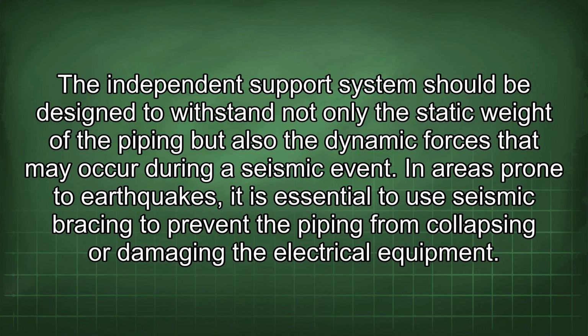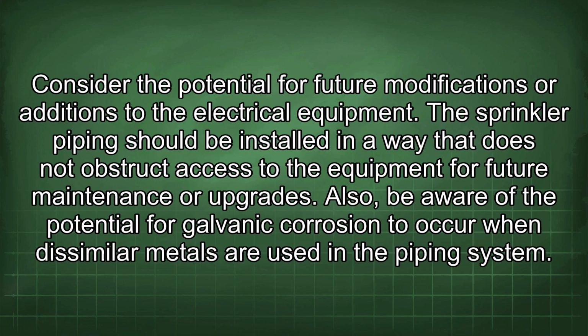Consider the potential for future modifications or additions to the electrical equipment. The sprinkler piping should be installed in a way that does not obstruct access to the equipment for future maintenance or upgrades.